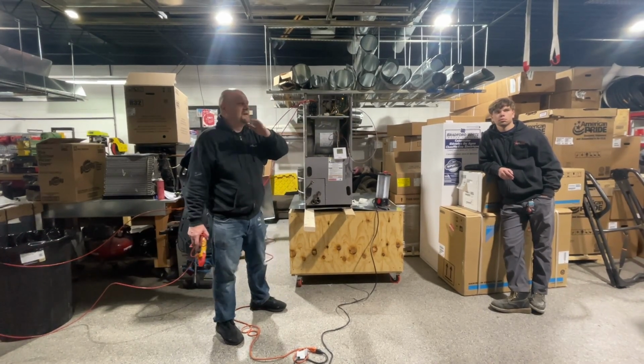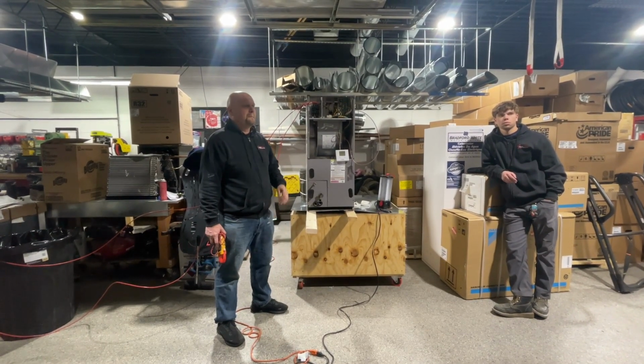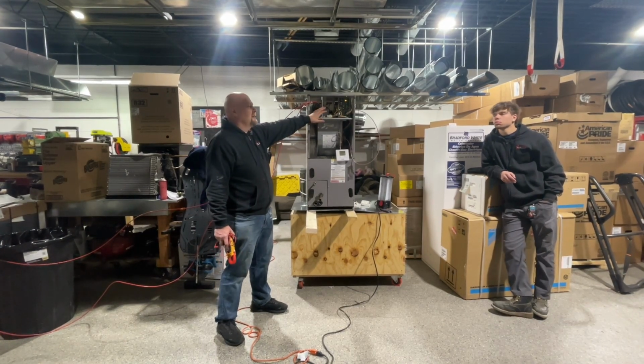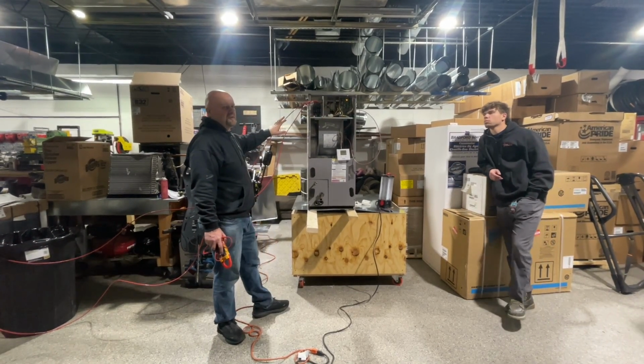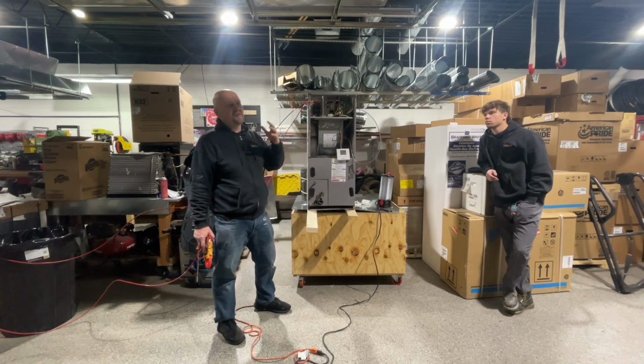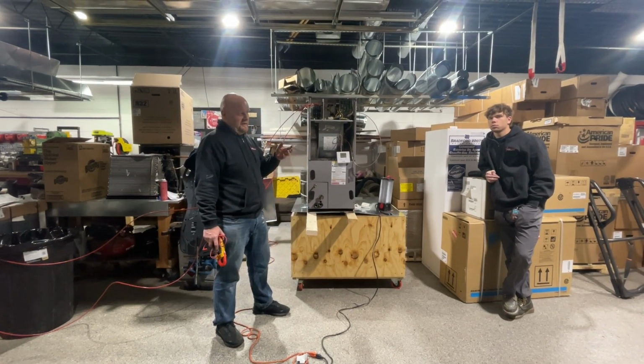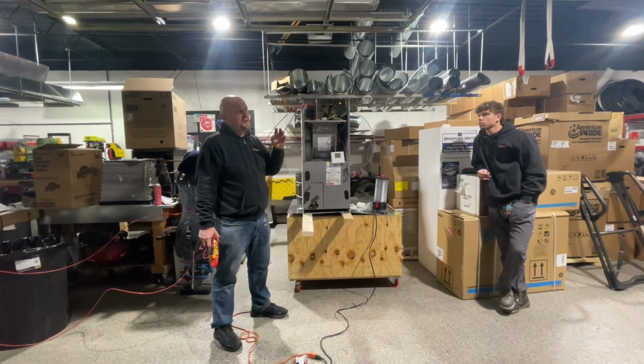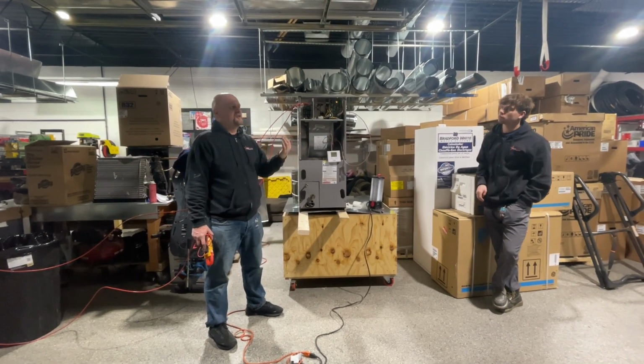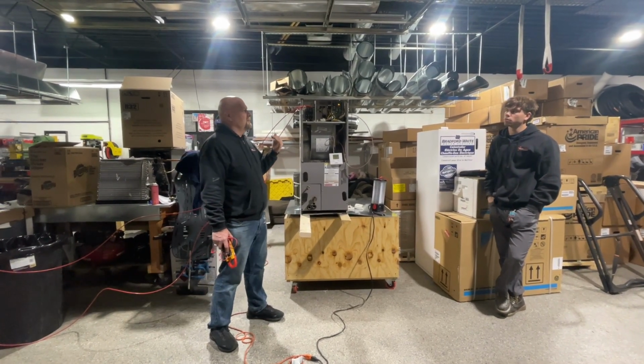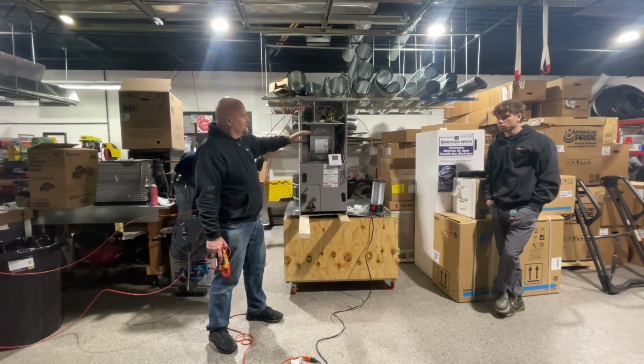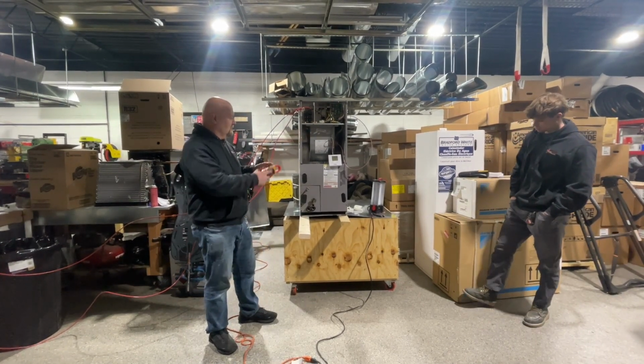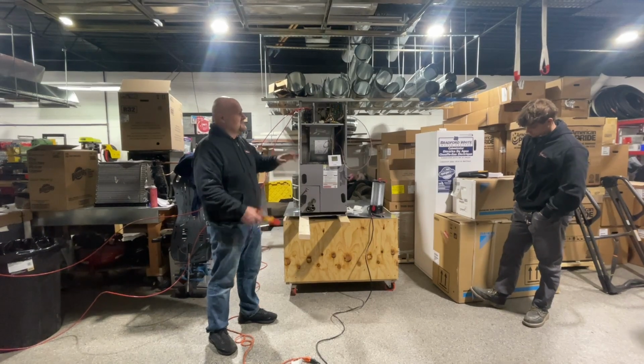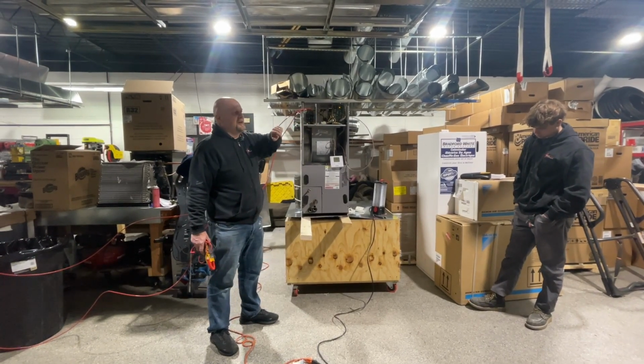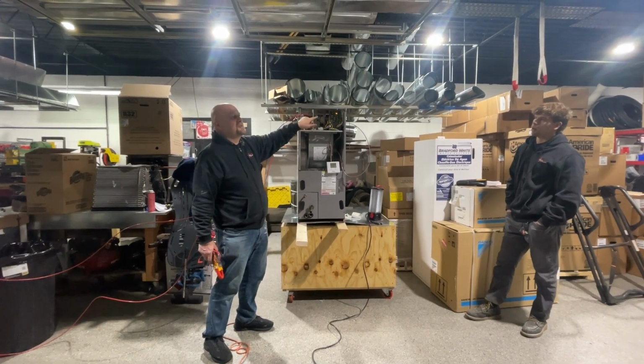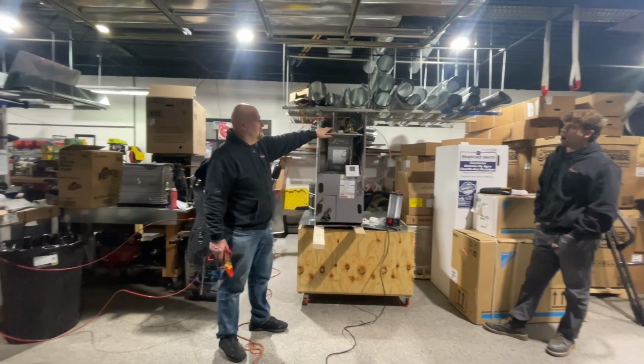If it's drawing too much current and the wire's too thin, it gets red hot. Either the circuit breaker breaks or the wire burns. There are only two possible things when you have over amperage, when you overdraw the power. So the circuit breaker is always going to be bigger than what you're actually drawing. If this is a 60 amp and you're drawing 55, 56, at some point this is going to start tripping all the time. That means there is a problem with this. Especially with older motors.